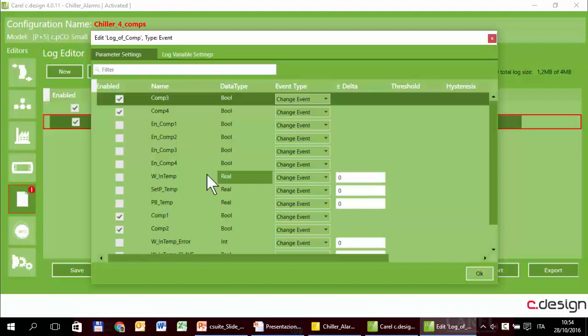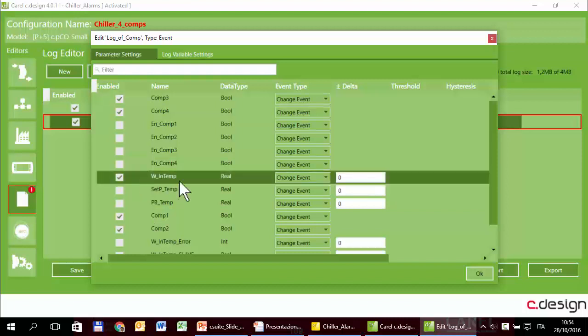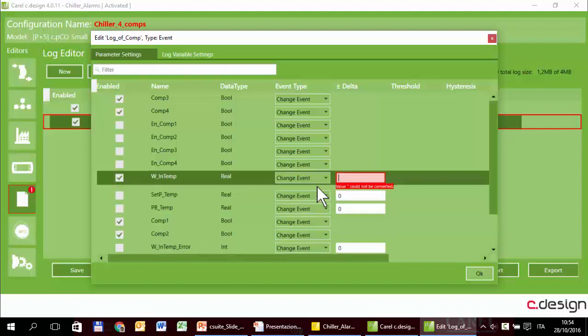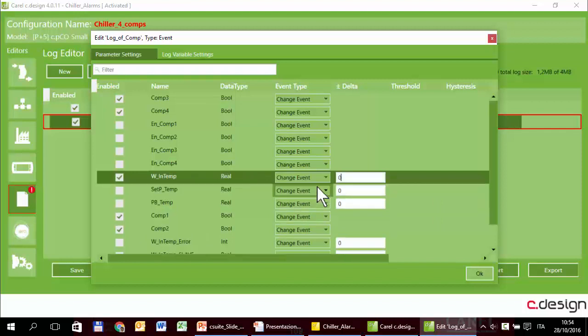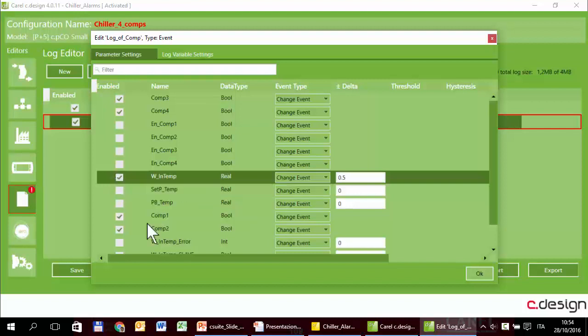For the real or integer data type, there is also the minimum delta. For example, in this case, only when the temperature changes by minimum one degree, or half a degree, the trigger is fired and the system will record the variables. For boolean variables it's not necessary.